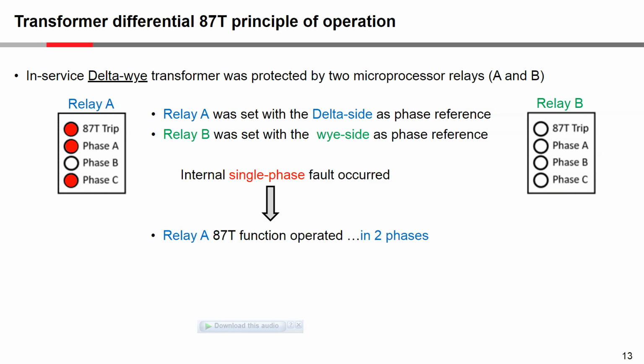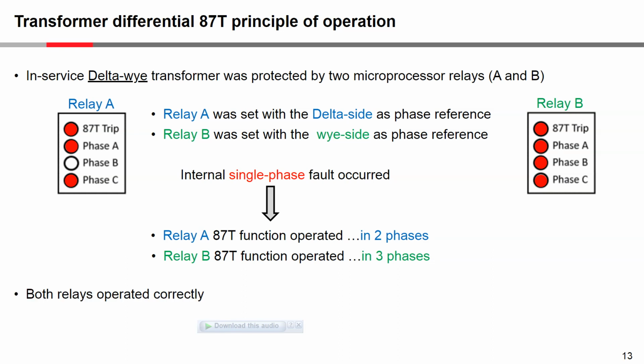If we have an internal single phase fault, you will see that relay A, which had the delta side as phase reference, will operate in two phases. You can see here we get the 87T trip, and we get operation in phase A and, in this case, phase C. But for the other relay, the relay that had the Y side as phase reference, we've operated in all three phases. So the 87T tells you you've had that 87T operation, and it's been in all three phases. The important thing to take away from this is that both relays operated correctly.